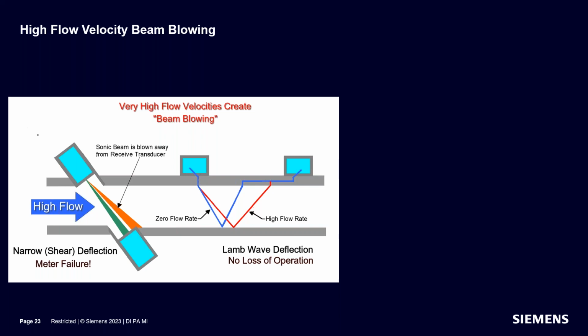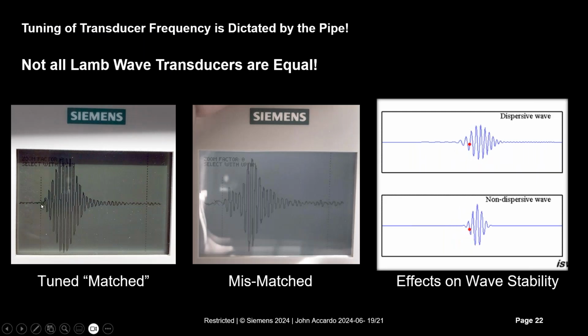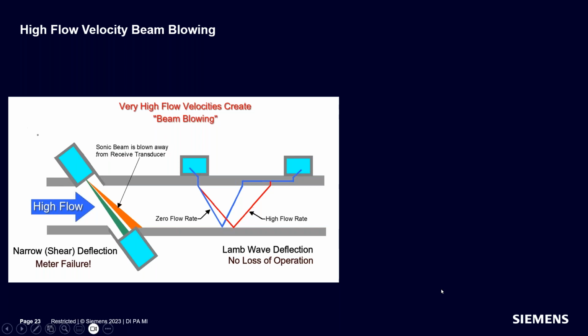So you get very large time difference between the up and downstream signals. Whereas with liquids, it's very unusual for the upstream signal and the downstream signal to be more than 1 cycle separated. Or if I go back to the previous screen, each of these waves is of 1 cycle. So it's very unusual for the upstream and the downstream, and you'll see that in one of the next slides, to be separated by more than 1 cycle. Whereas with gas, it's very common to be separated by multiple cycles.